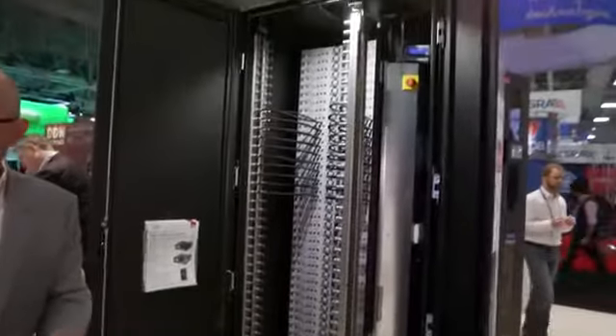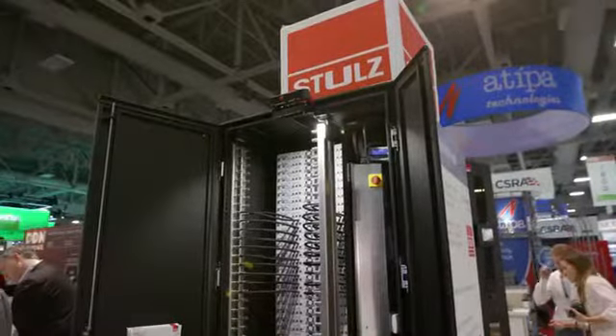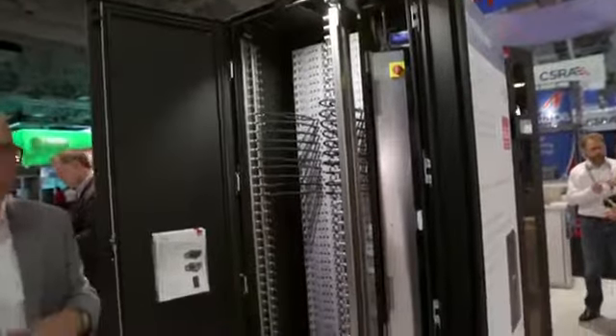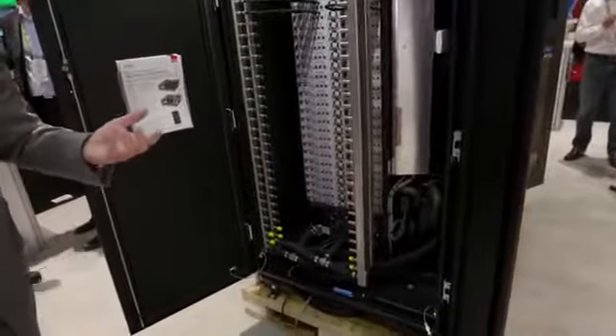The key element here is that this is a fully integrated solution. All you need to bring to this rack is some sort of liquid chilled water loop or a dry cooler loop that you have on your building site, and power. That's it—it's a complete all-in-one solution, and it's a structure that can be located anywhere in a building, so you don't need any kind of conditioned room or conditioned space. It could be installed in an office space or a warehouse environment.